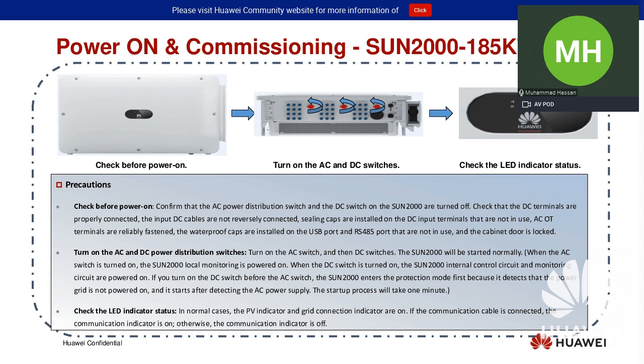And if you left any PV input unused, make sure you put the lock or the provided cap onto that PV input, to protect it and you from any kind of damage. Also make sure the RS485 or communication connectors are properly installed, the USB port is closed, everything is properly sealed, and the AC compartment is properly locked, so there are no problems. Nothing, no insect or anything, can go inside that inverter.